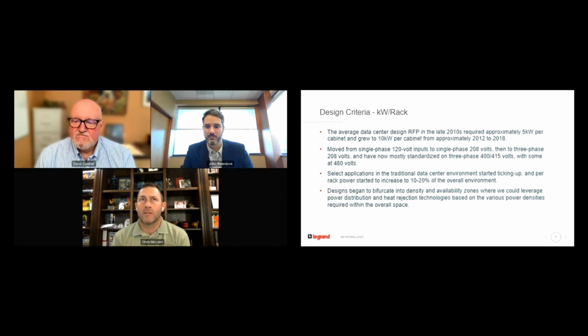As the network appliances changed, we started seeing the environments shift, where the L630 yielded to like L2120s, again 5 kW, but now 3-phase power, like you said. And we started proliferating entire rooms with that, and then it jumped. It was now 3-phase 30, 3-phase 40, 3-phase 50 and 60, but only 7 to 10% of your environment. The power density did come, but not at scale.